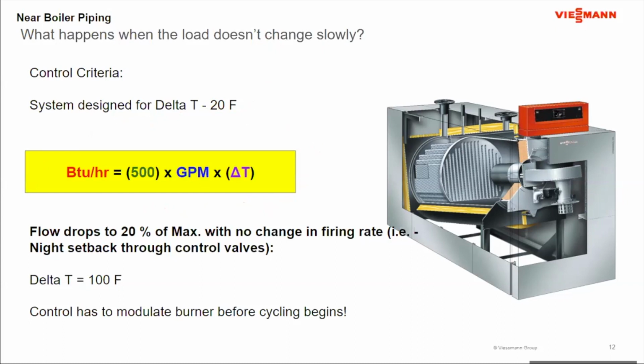The ones that I've had discussions with people over a lot of times centered around night setback, where all of a sudden, say at 5:30 at night, they reset the ambient temperature in the building down 10 degrees, say from 70 to 60 degrees. And at that very moment, 80% of the control valves in the building go closed. All of a sudden, the flow rate drops from 100% down to 20% or even lower. And what happens is, when I drop that flow rate, initially the BTUs per hour are not going to change.